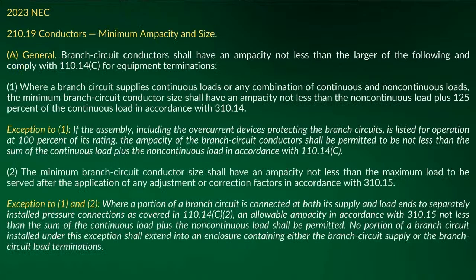And then when you look at 210.19(A), just like I was talking about, in the general requirements in A1, it talks about where a branch circuit supplies continuous loads or any combination of continuous and non-continuous. It tells you to take the continuous load at 125% and the non-continuous loads at 100%. And then if you drop down to A2, you'll see that it's separate and it doesn't mention anything about continuous and non-continuous load. It just says the adjustment and correction factor. So therefore, you're doing it at 100% of the load.